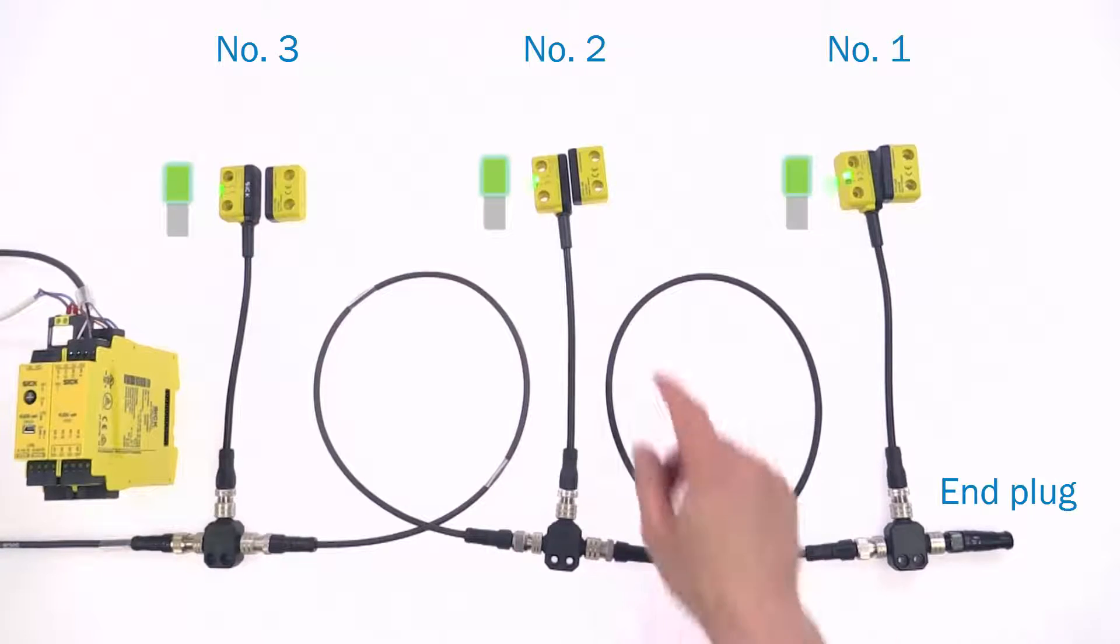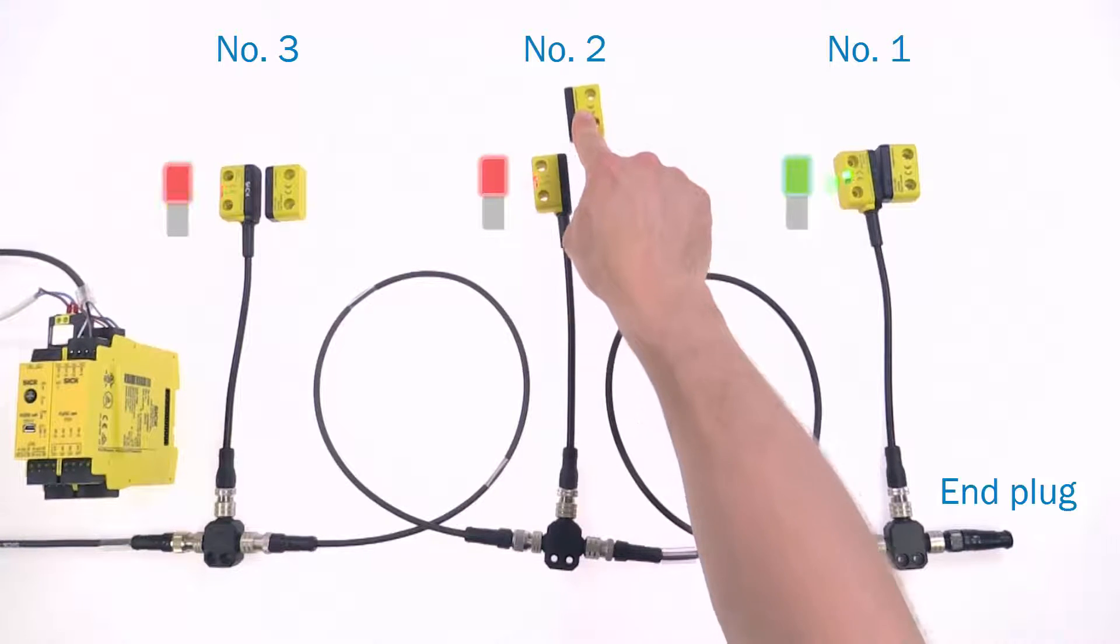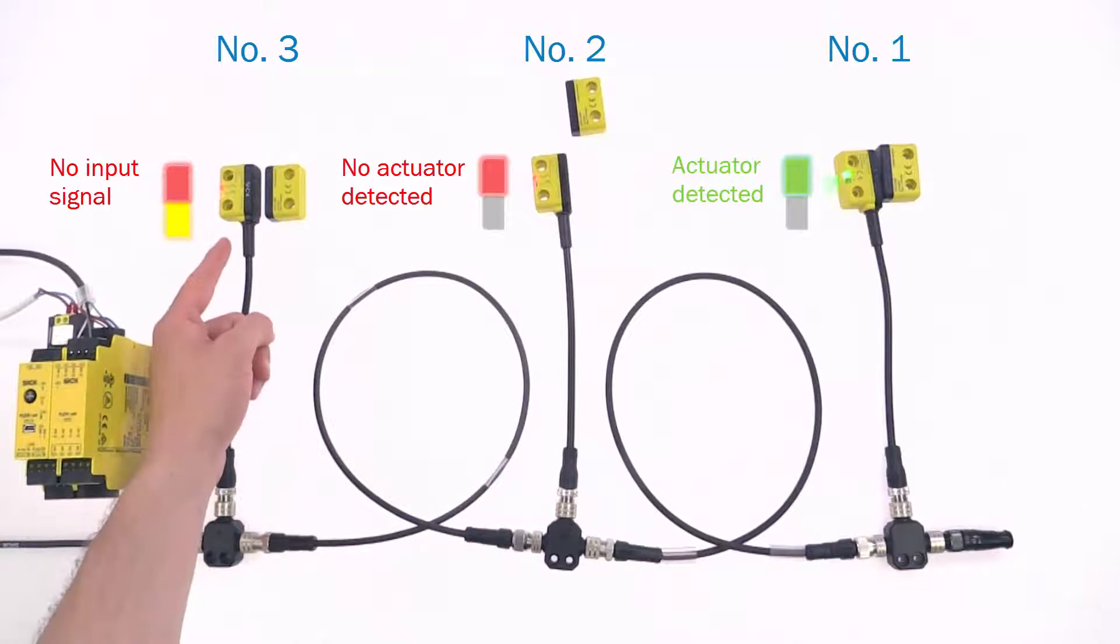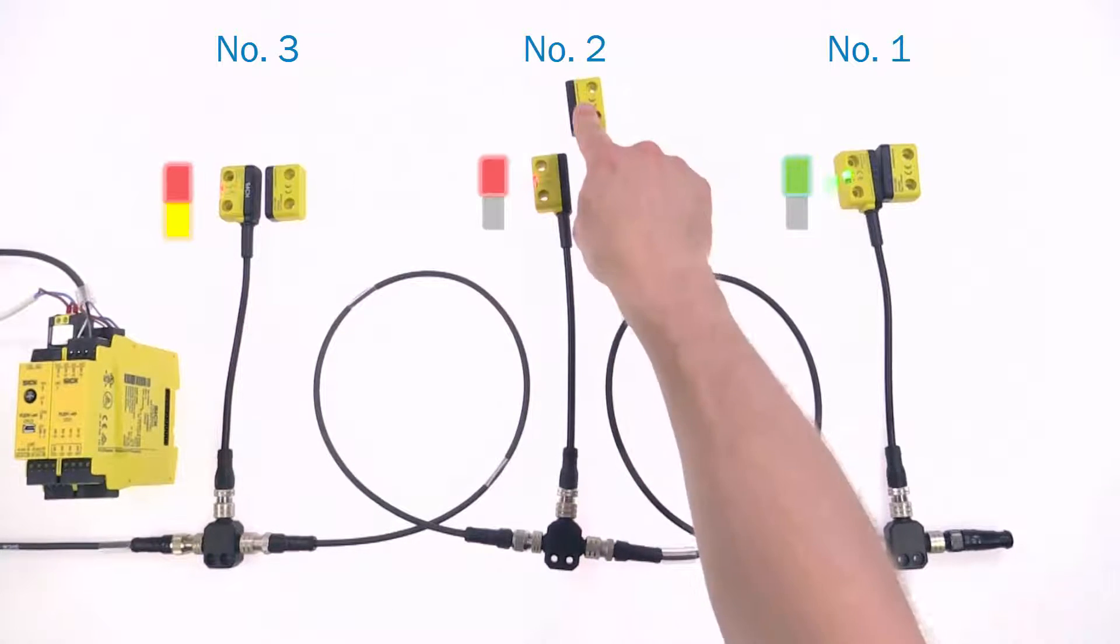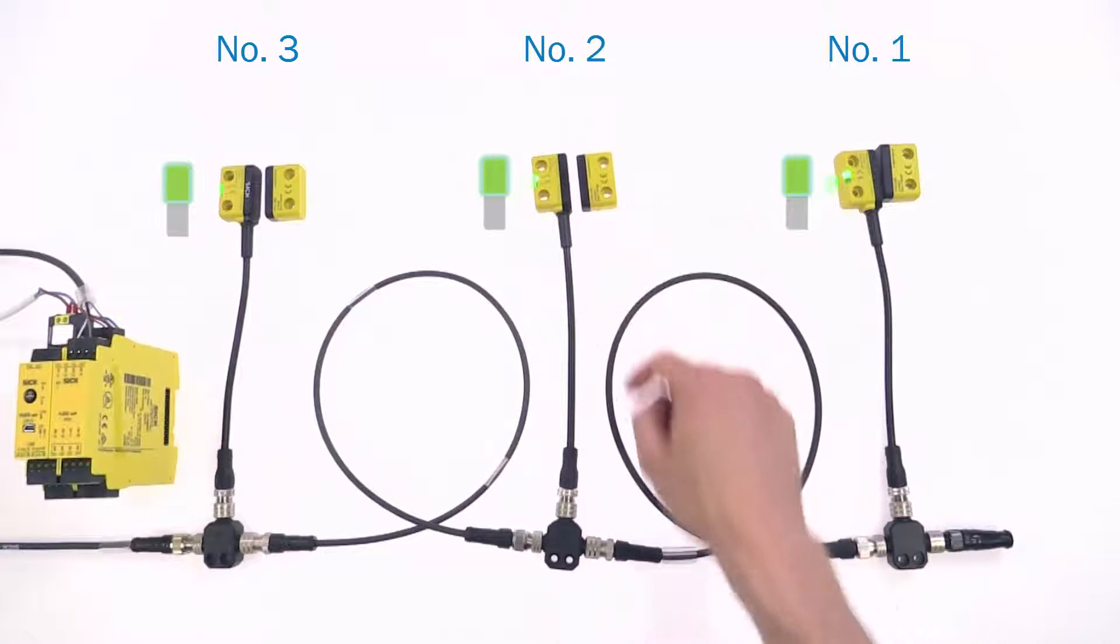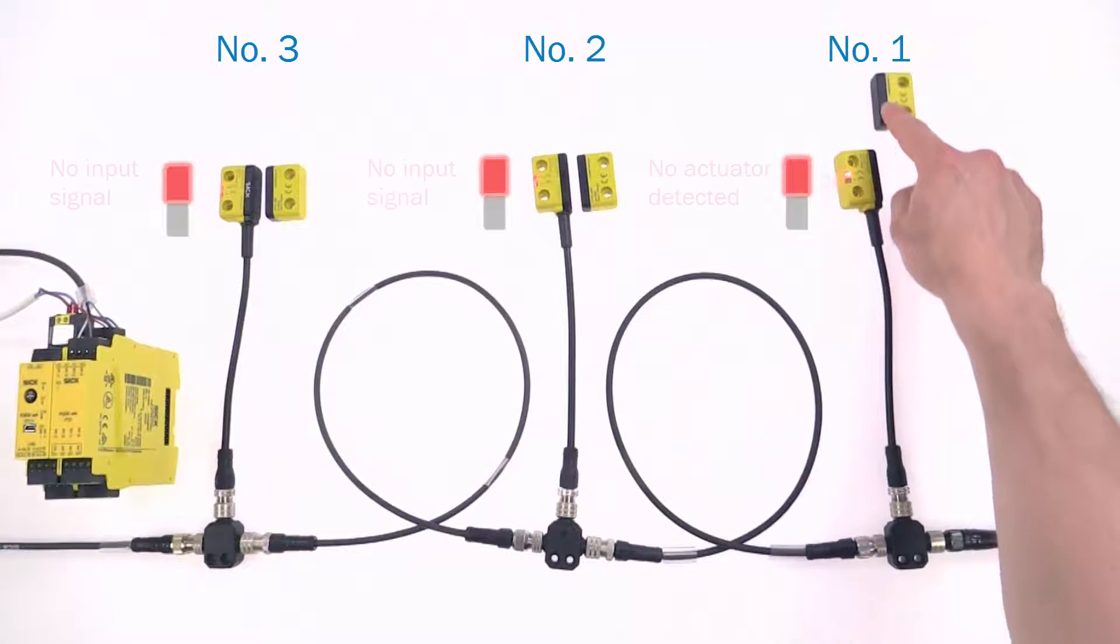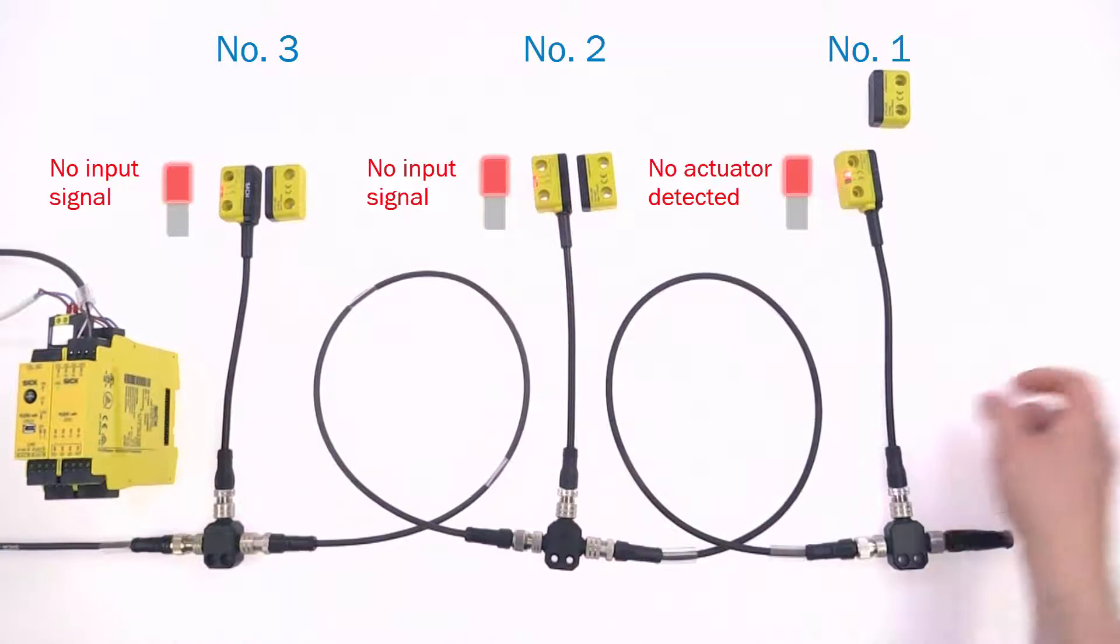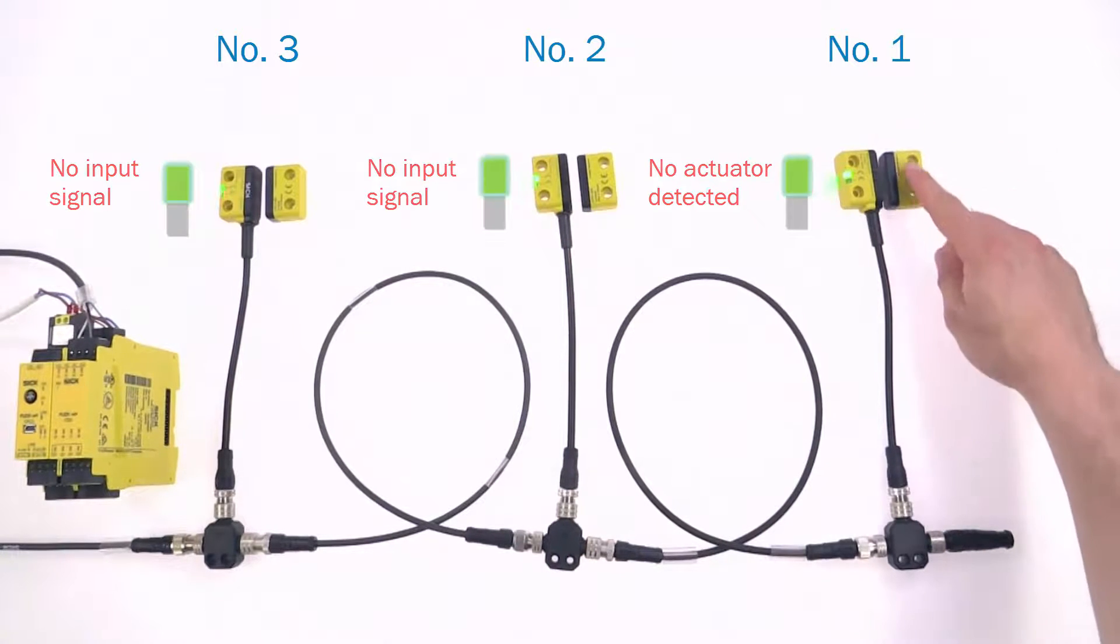If no actuator is present, or if there is a fault, the OSSD outputs of sensor 2 are low. Sensor 3 will get no input signals and will also keep its OSSD outputs low. If the OSSD outputs of the first sensor are low, all following sensors report that they get no inputs.